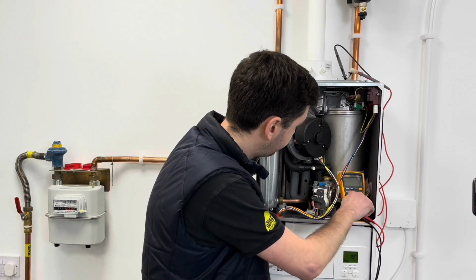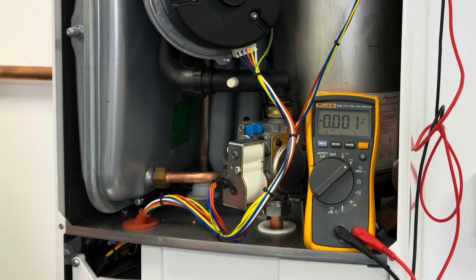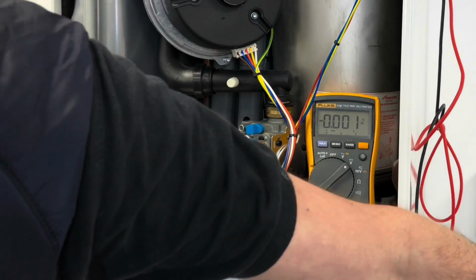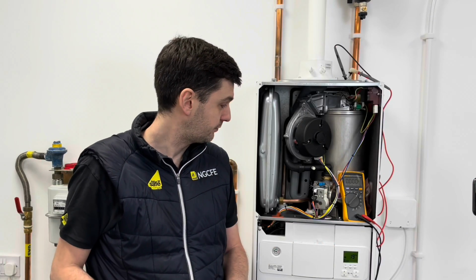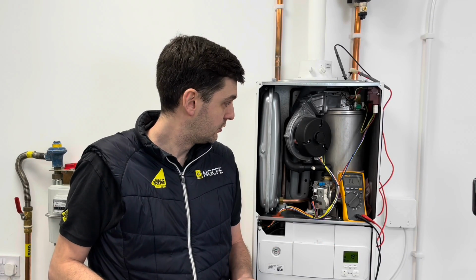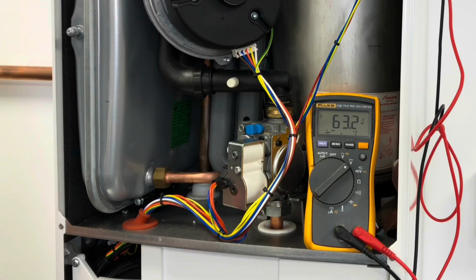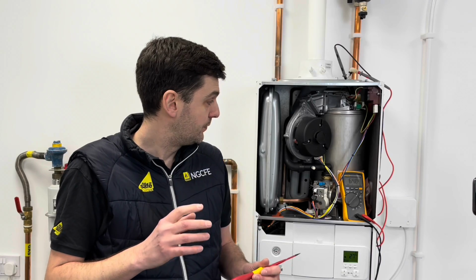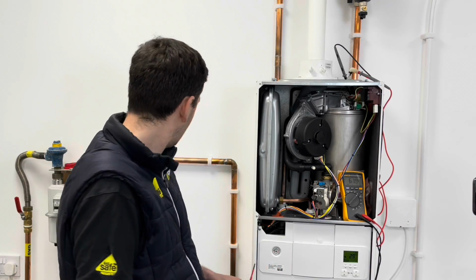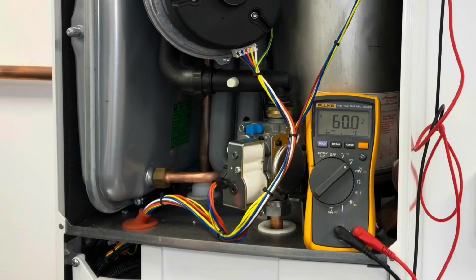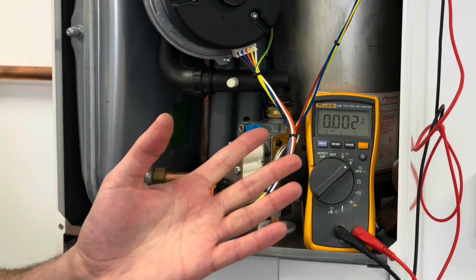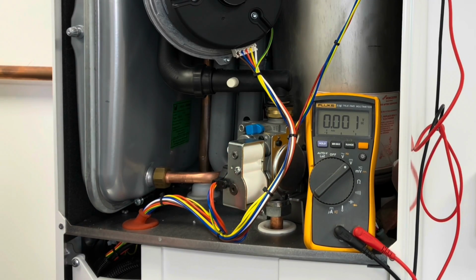Hopefully we've got a healthy DC reading coming back and we'll know that we've got a flame established. So let's try that. Set the multimeter to volts DC, and we'll turn our boiler on. So that's lit, and straight away we can see we've got 63 volts DC current travelling back. So that would indicate that we've got a healthy flame, the flame's established and the board is reading it. So if for whatever reason we were to turn the gas off, we've now lost the voltage DC, and the board has recognised that, and it's gone now to a fault.